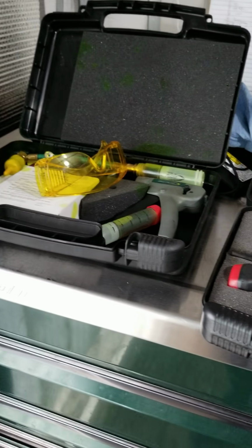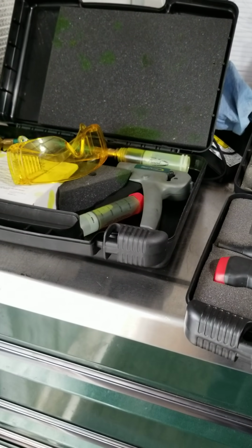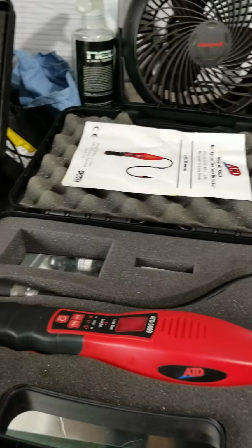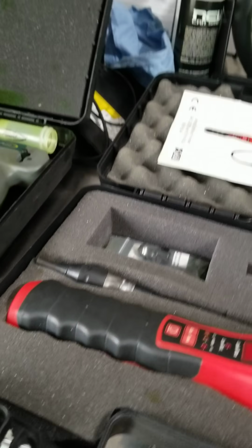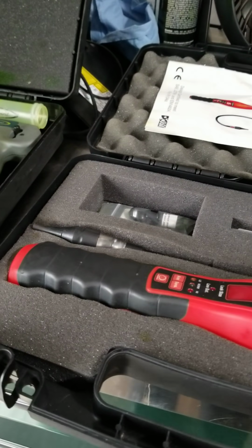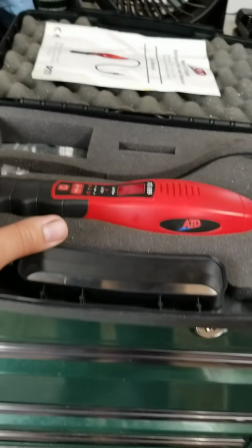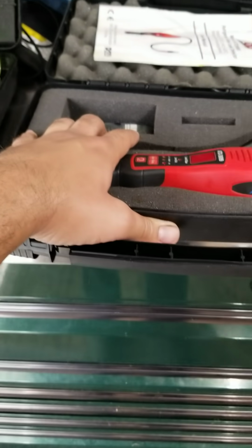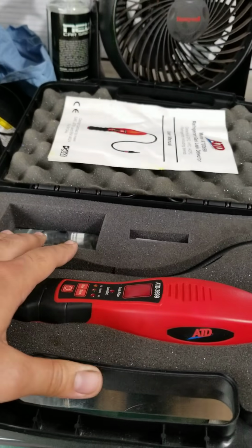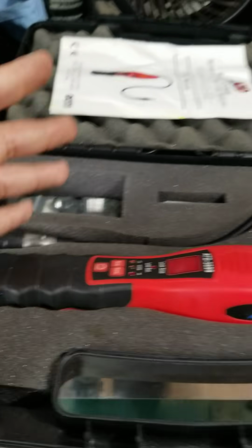Sometimes I just charge the system with compressed air and use a little spray bottle with soapy water and watch it bubble up. Now, the reason they say you shouldn't do that is because you don't want to introduce any moisture into the system, in the compressor and the lines or whatnot, and then that can give you issues. But normally it's just a little bit of air, pressurize it, close the valves, and then go to work. And sometimes you can find it that way. I used that method a couple weeks ago to find a leak on an RV, and I found it, I repaired it, and that's the method that I use.